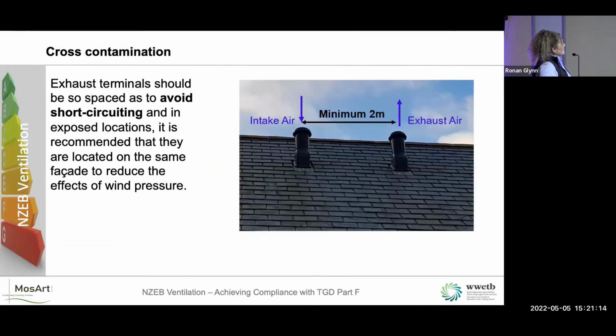Again, we want to avoid cross-contamination, so you don't want your exhaust air coming back in into your intake air, okay? And that has been an issue with machines. Say, the supply rooms are getting the smell of air freshener in an office block. It was an example given to me. The supply rooms, the office blocks were getting the smell of air freshener. And what happened was the exhaust was on the windy side of the intake, so the air was blown back in again. So they just needed to change them around a bit.